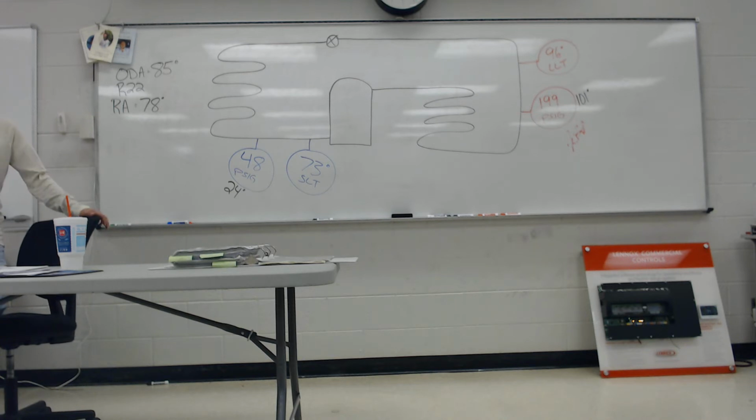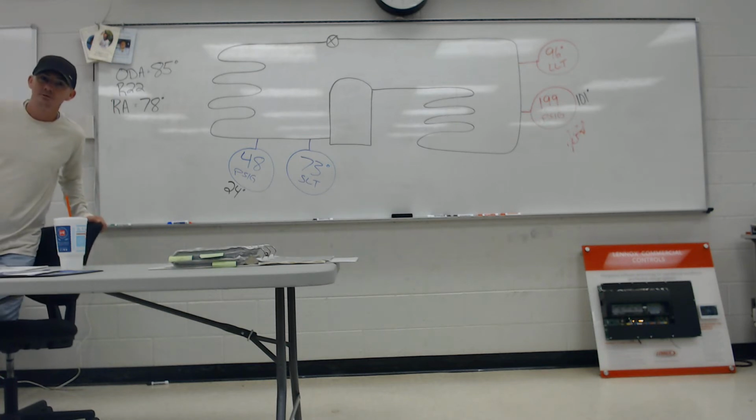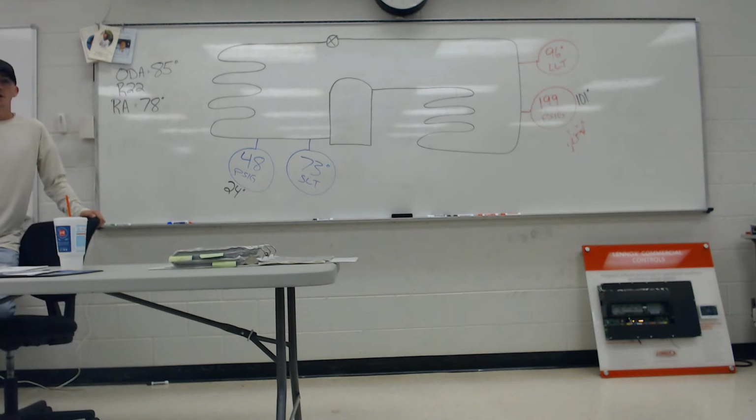I'm gonna be really honest with you guys. I hardly ever take a temperature split, and so I go against the grain on a lot of people. If you guys did any PMs for a company and they were like, if your supply air, return air split is okay, don't even hook gauges up, I'm gonna call bullshit on every single person that brings that up. I don't roll that way ever.